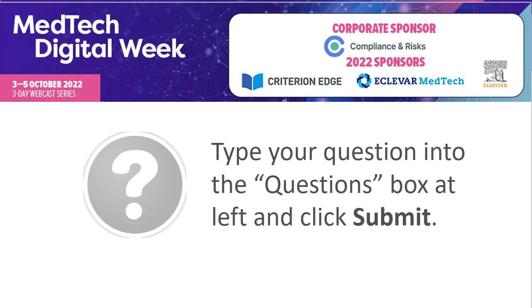That's where it's made. So in the claims section, claims are linked to clinical benefits, and clinical benefits must be supported by clinical data. That's the easiest way I can say it. So if a manufacturer claim says that our device does something faster than something else, then that word faster is the claim word in there. So where do you have safety and performance data showing that your device does something faster or results in some sort of improved outcome?